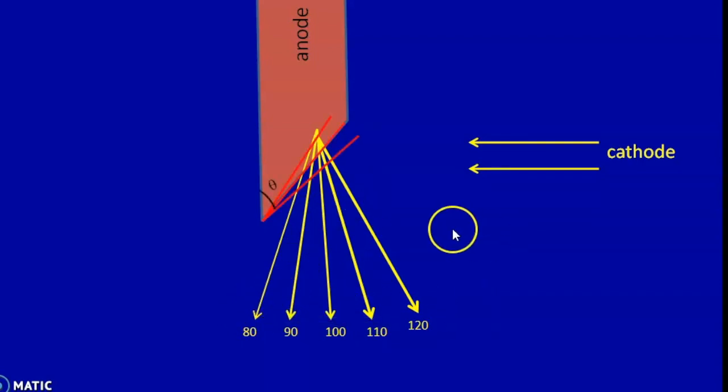Finally, the anode angle also plays an important role in increasing or decreasing the heel effect. When the anode angle decreases, more X-rays are made to traverse through the substance of the anode, through the heel of the anode, thereby increasing the effect. And increasing the anode angle far away from the main substance of the anode reduces the heel effect.